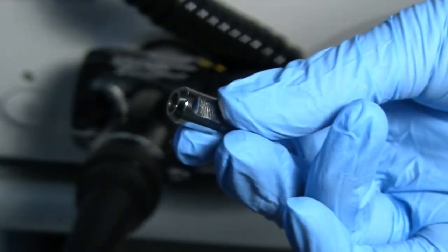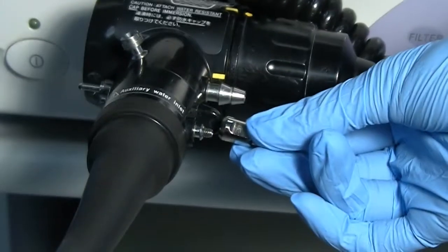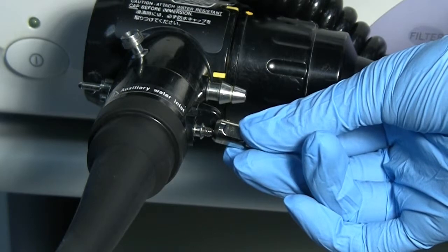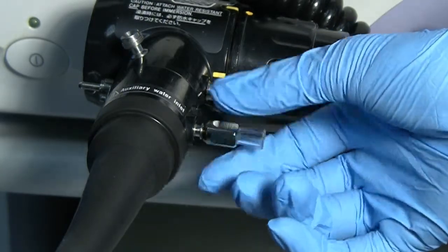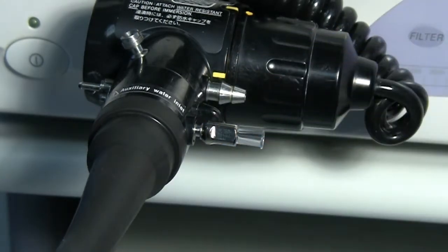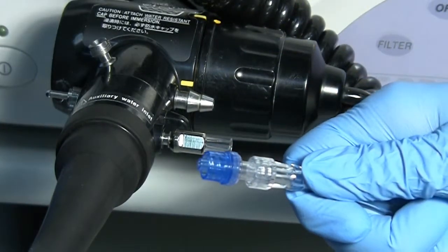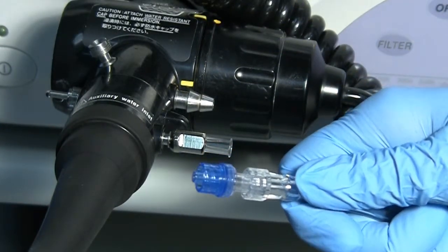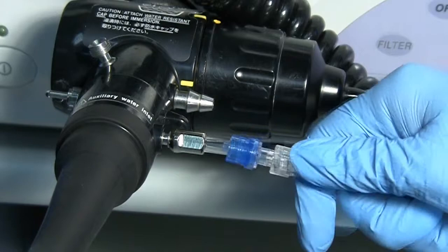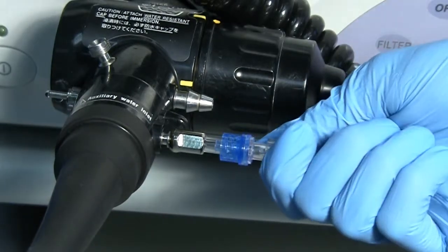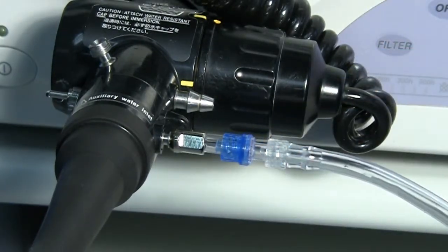As with each EndoGator, a connector must be used to connect to various scopes. The 24-hour use auxiliary water connector is shown here. The auxiliary connector screws onto the water inlet clockwise. After the connector is secured to the scope, take the distal tip of the EndoGator tubing and luer lock it to the connector. The blue connector you see here is a one-way or anti-reflux backflow valve.